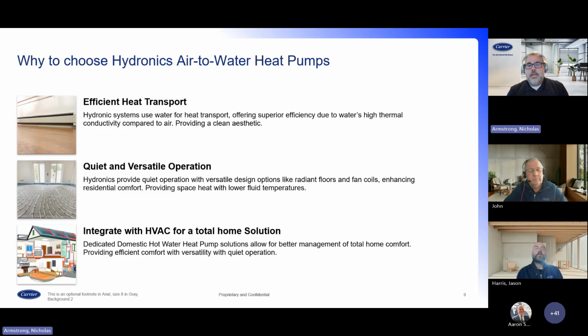So to talk a little bit on the hydronic side, specifically the product that we're talking about here, this air to water heat pump system. The first bullet on this slide here talks to the efficiency of that heat transfer, and that goes back to the previous slide where I'm talking about the thermal conductivity of water being 23 times higher than air. The second piece here is it's quiet, so it's unlike a forced hot air system. It operates silently. It's got flexible designs, whether it be the radiant floors or fan coils, zoning strategies, all of that's available as part of the solution.